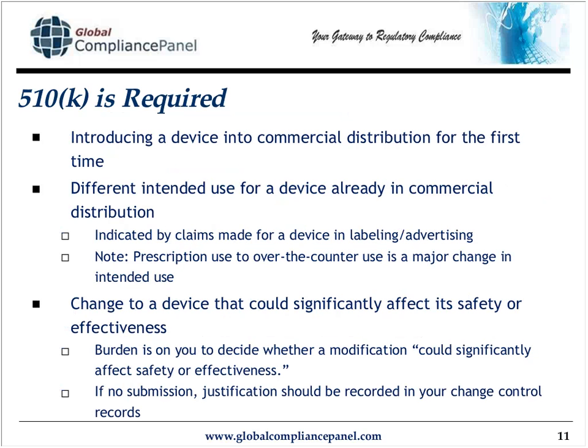There are several situations in which a 510K is required. The no-brainer of these is you're introducing a brand new device for the first time. Second of these is you have a device that you're already selling and you're changing the intended use. The intended use is usually indicated by claims made in the labeling or in the advertising.